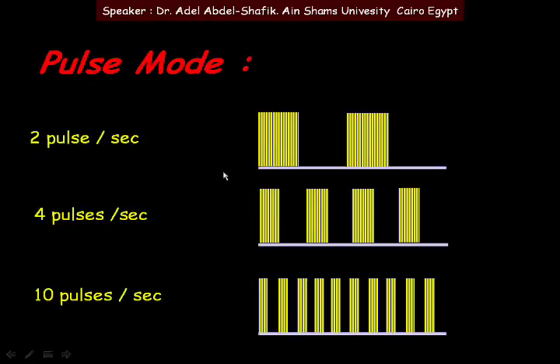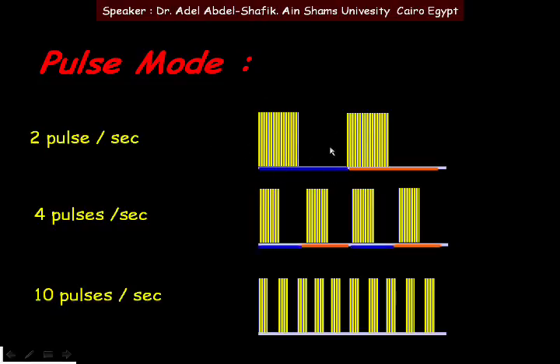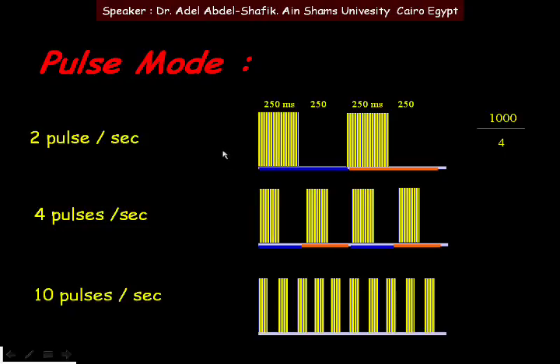Pulses can be adjusted for a certain number per second — for example, two, four, or ten pulses per second. At two pulses per second, we have two cycles in one second. Each cycle is divided into half on and half off, giving four intervals — two on and two off — each interval being 250 milliseconds.